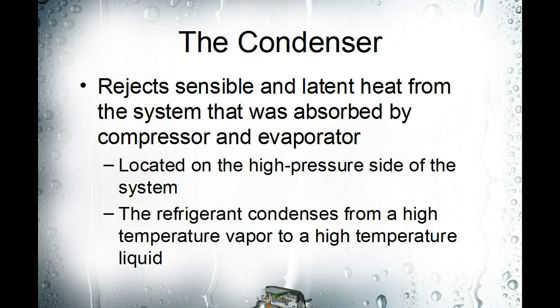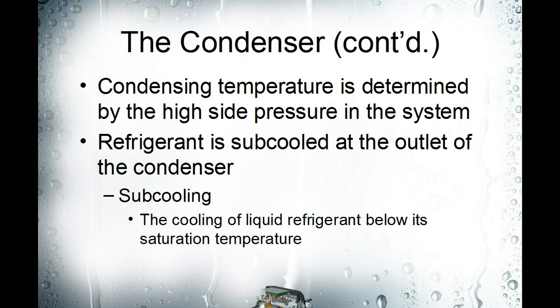The condenser is where we undo all of the sensible and latent heat that we absorbed in the evaporator and dump it to the outside. The condenser is located at the outlet of the compressor and it is the high side, pressure side of the system. The condensing temperature — the saturation temperature of the refrigerant in the condenser — is determined by the high side pressure.